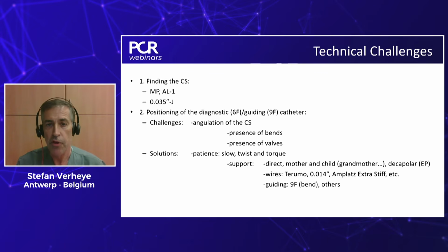And the multipurpose, you can easily slide it into the coronary sinus all the way down, remove your wire and make a firm, nice injection. That allows you to have a good idea of the sizing, one, and second, where am I going to put my reducer? So the landmarks here are important. You want to be as close to the ostium of the coronary sinus, but you don't want to be too close because then the size becomes too large and you cannot properly implant the device.